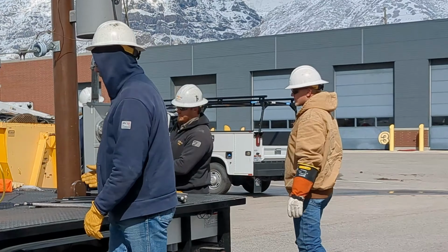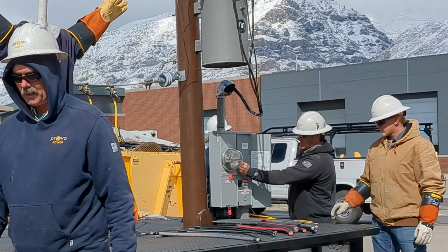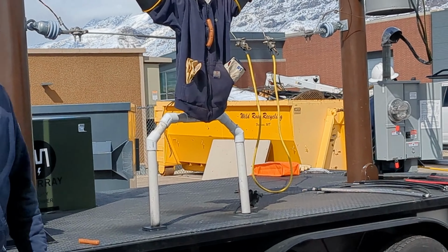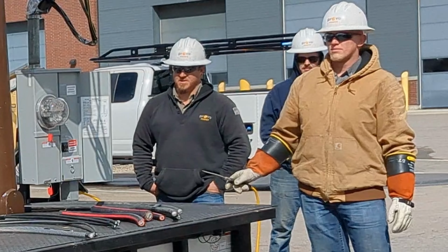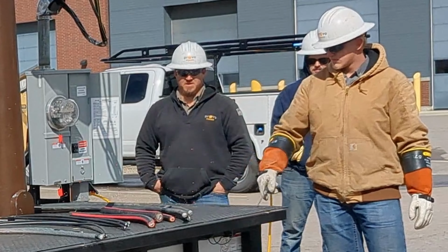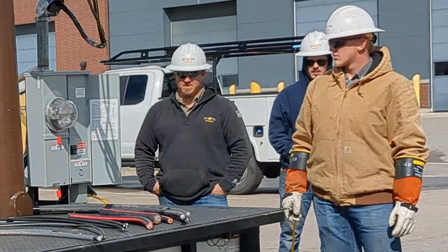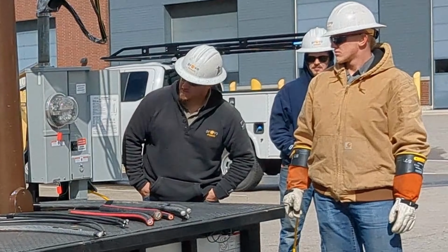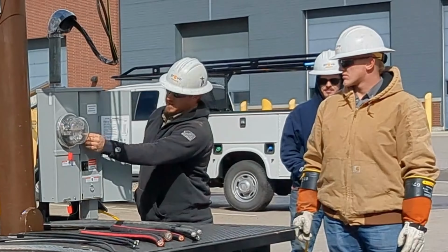Okay, and this is a new trailer, and it's got a GFI on it and a 20 amp breaker, 120/240. So this is just a 20 amp breaker. Trip it. Now we'll plug it into the GFI.